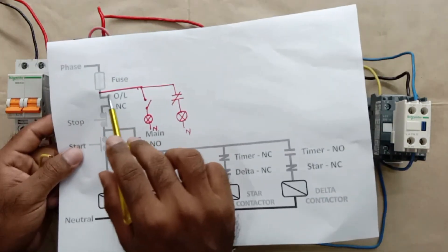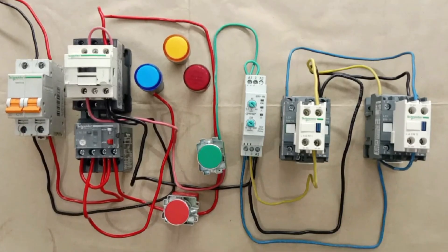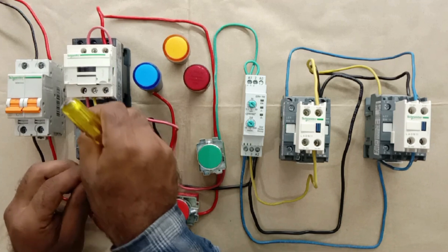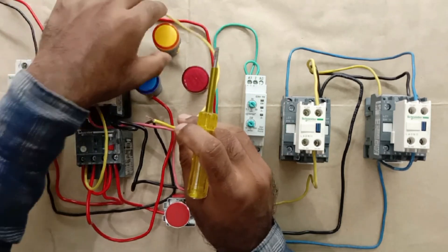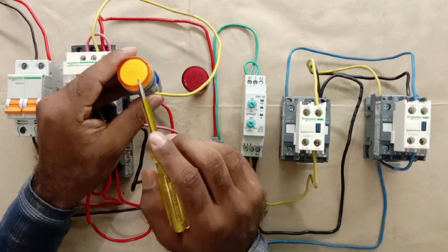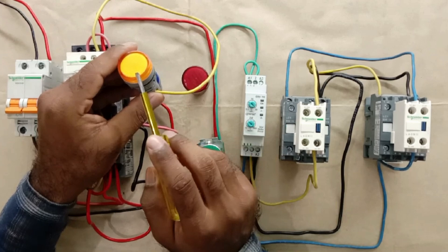The power supply coming to the overload relay — we loop this to the two terminals. We loop a wire from the NC contact of the overload relay and connect it with the NC contact of the main contactor. Then we connect a wire from the NC contact output to the off indication lamp — the yellow lamp. Normally we use a green indication lamp for off indication, but right now I don't have a green one, so I used a yellow indication lamp.